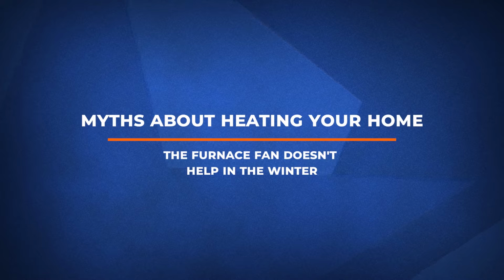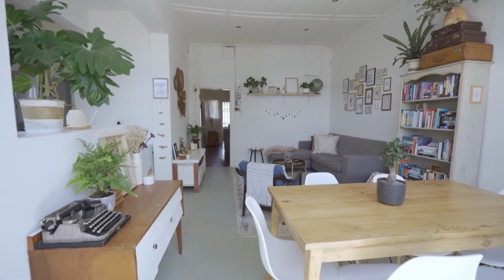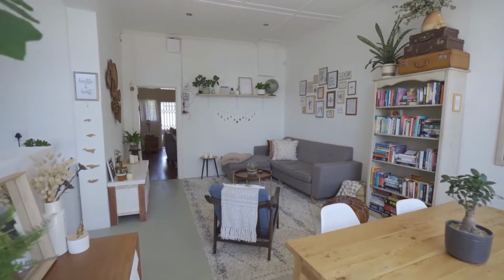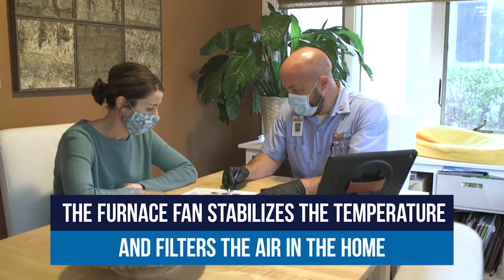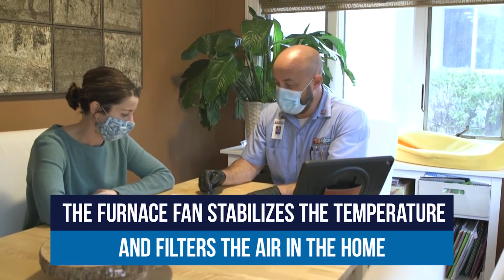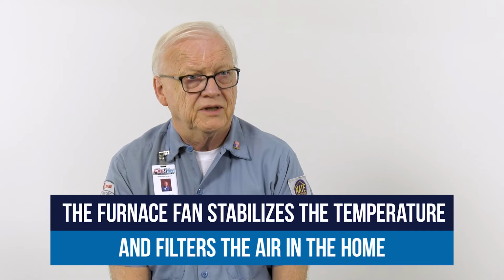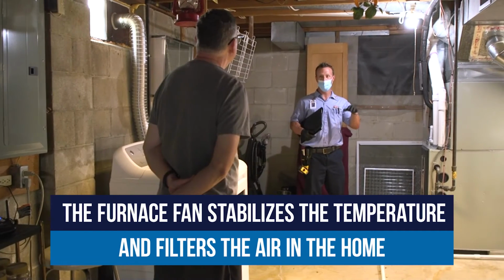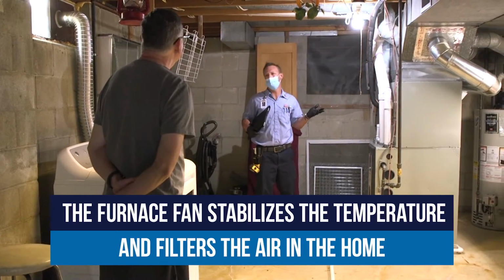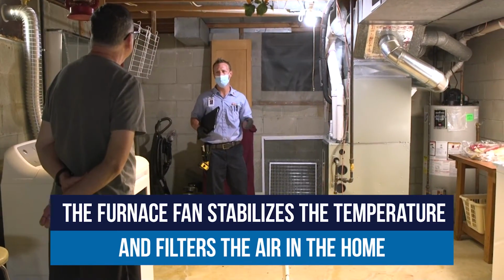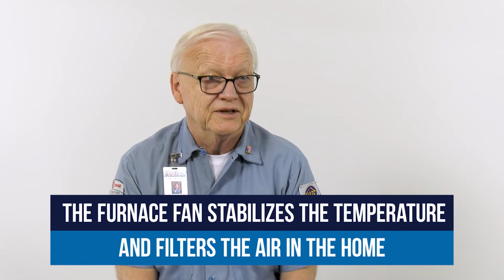So the next myth we see is that fans don't help in the winter. Running a fan continuously on a furnace, in my opinion, always helps, because now you're circulating the air throughout the whole house, and if you have hot and cold spots, that will become much less of an issue because you're stabilizing the temperatures in all the rooms. And then the equipment, the air conditioner or furnace, will come on and off as needed, but you're still circulating the air, which, by the way, when you do that, you're also filtering it. So that's helping keep the system clean and so forth.